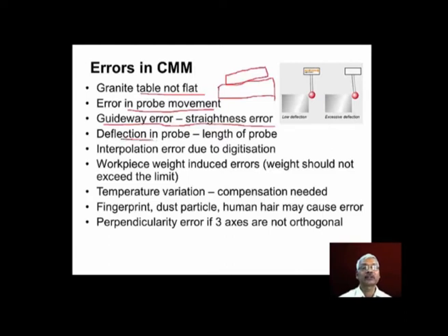And then deflection in probe. If we use unnecessarily long probes, it will bend too much, and because of this deflection, error is introduced. And workpiece weight induced errors. So when we keep the workpiece on the granite table, if the weight is too much, then the granite table may deflect like this. Because of this, the measurement error will be introduced.